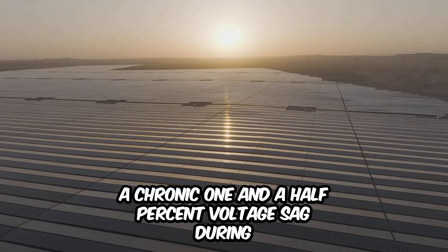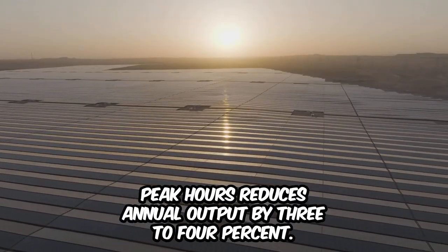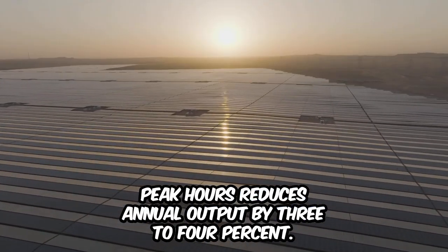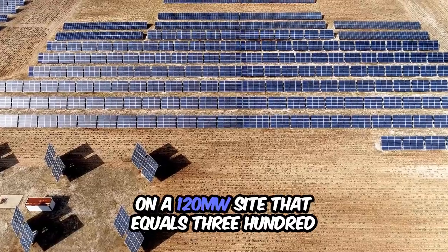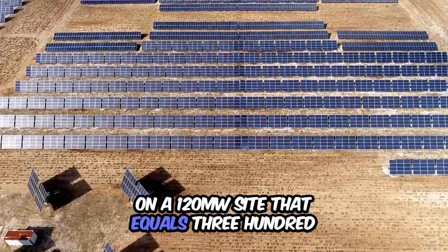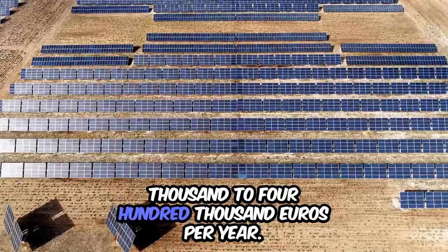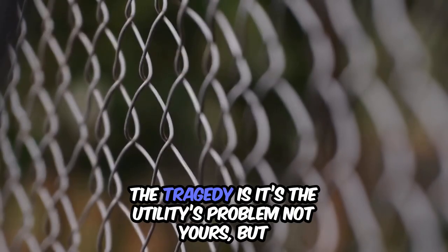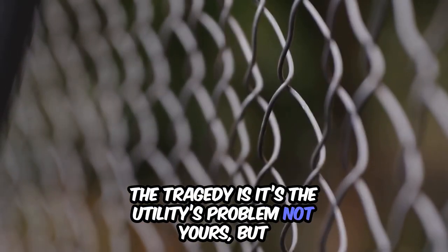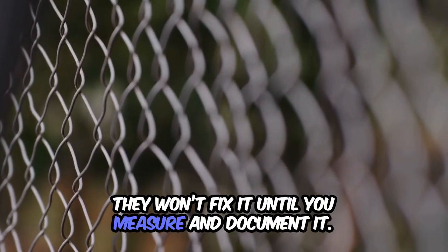A chronic 1.5% voltage sag during peak hours reduces annual output by 3 to 4%. On a 120 MW site, that equals 300,000 to 400,000 euros per year. The tragedy is, it's the utility's problem, not yours, but they won't fix it until you measure and document it.